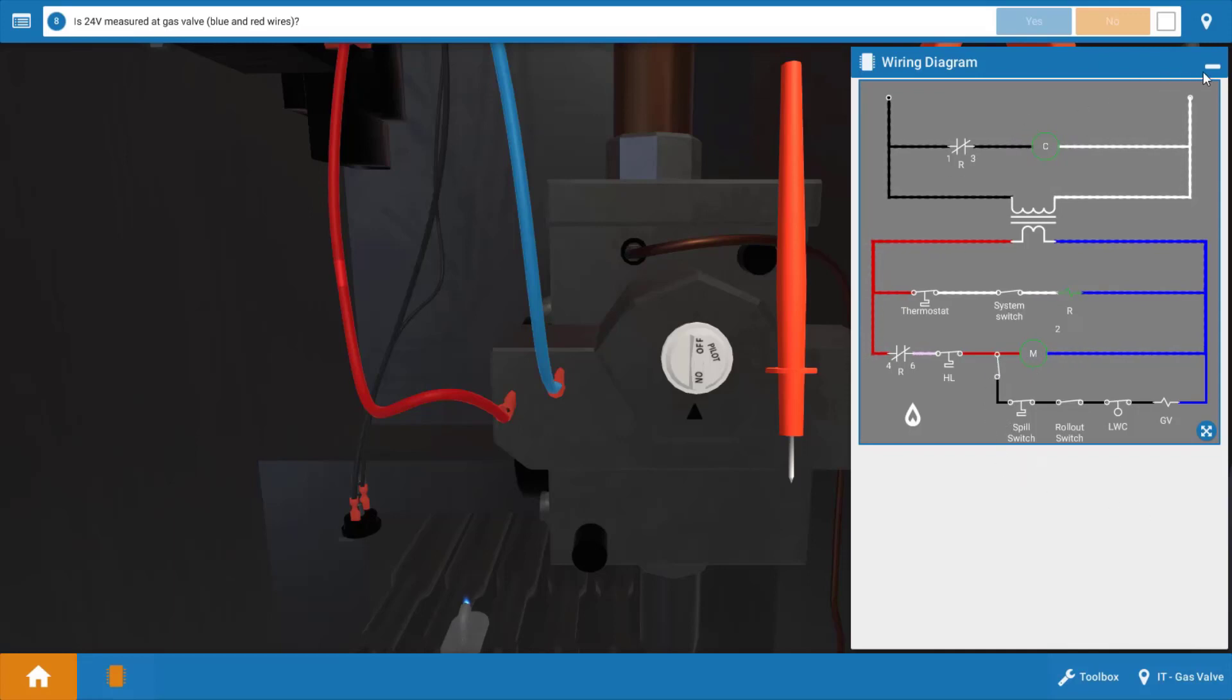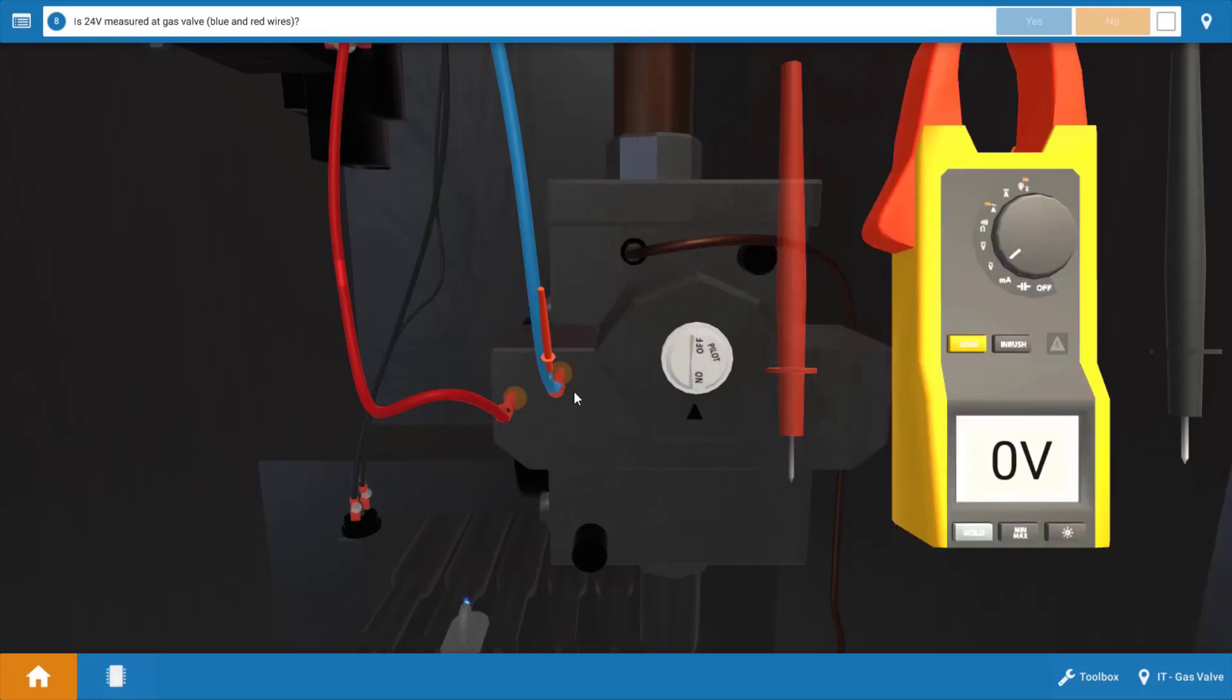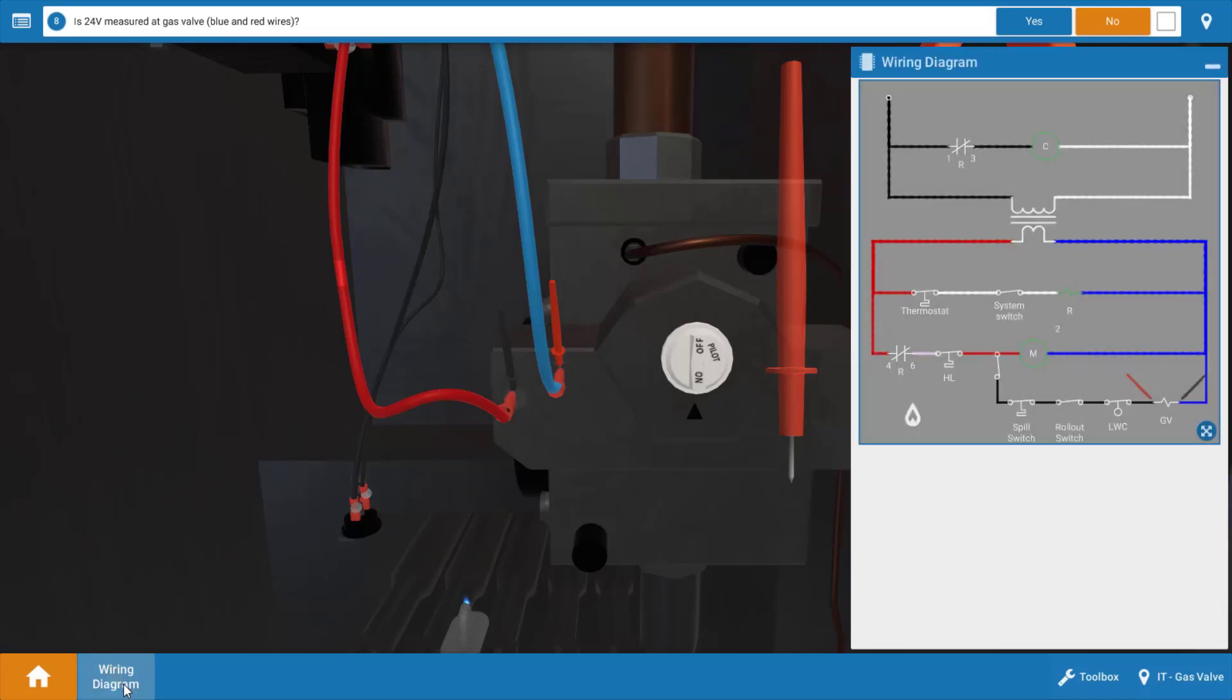So our next step is to check for voltage at the gas valve. So what I'm going to do, I'm going to place the leads across these glowing orange hot spots at the gas valve coil connection, and when we do this, our meter reads zero volts, which means the gas valve is not receiving voltage.